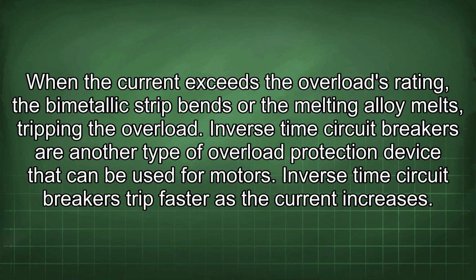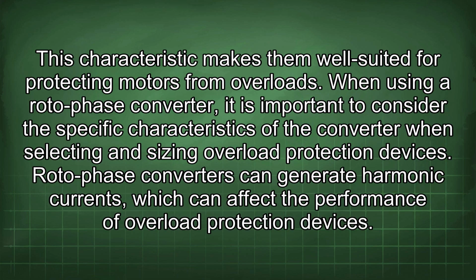Inverse time circuit breakers are another type of overload protection device that can be used for motors. Inverse time circuit breakers trip faster as the current increases. This characteristic makes them well suited for protecting motors from overloads. When using a roto-phase converter, it is important to consider the specific characteristics of the converter when selecting and sizing overload protection devices. Roto-phase converters can generate harmonic currents, which can affect the performance of overload protection devices.